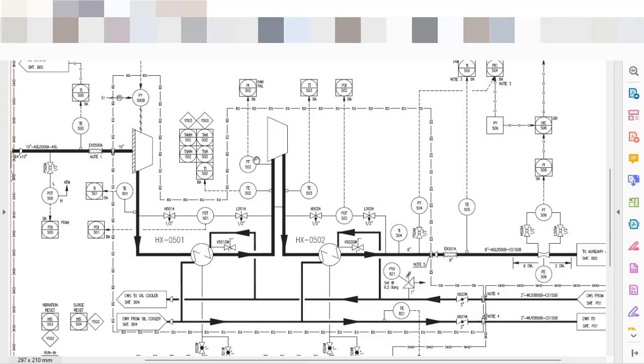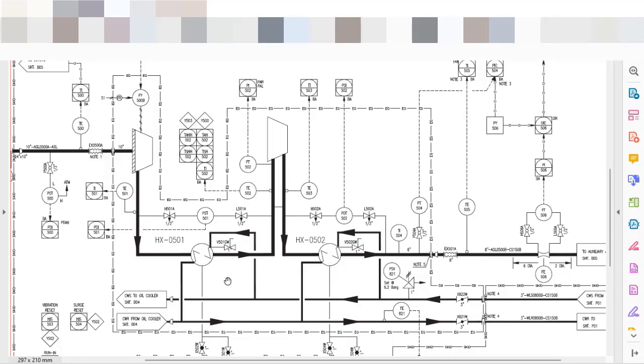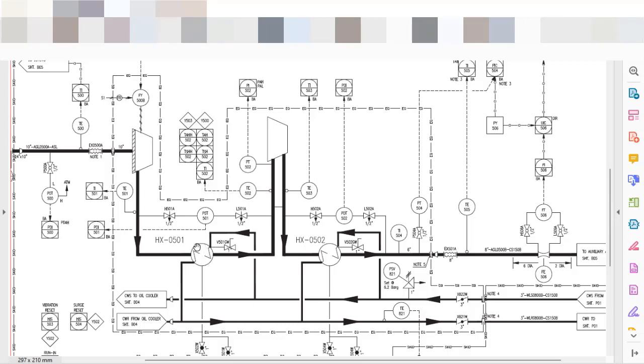Observe that in this case, I don't have a vessel separator to collect the condensate of the process. I don't have for two reasons. In the operating conditions of this equipment, I do not expect to have a lot of liquid condensating or removal of condensate from my air. So what was done here is pass the air at the shell side of the heat exchanger and consider the removal of condensate at the shell side of the heat exchanger. I am able to do that because the amount of condensate to be removed is not too much, so I will not increase too much my heat exchanger.